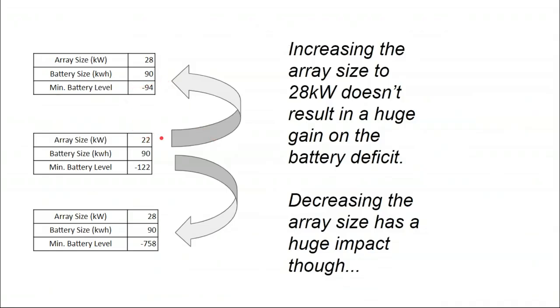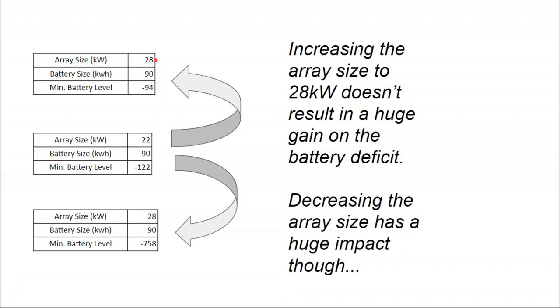So that's why it's important to build your own model and set up little toggles to look at the extremes. What happens if I go from an 18 to a 22? What would happen if I go from a 22 to a 28? I can see that by increasing my array size from 3 pallets to 4 pallets, I can reduce my battery bank by another 30 kilowatt hours. So is that worth it or not? Maybe, maybe not.